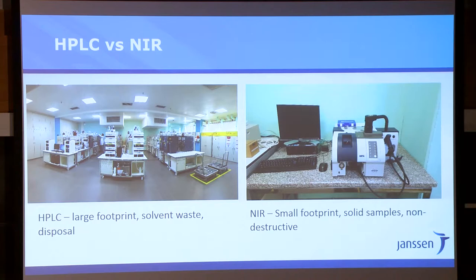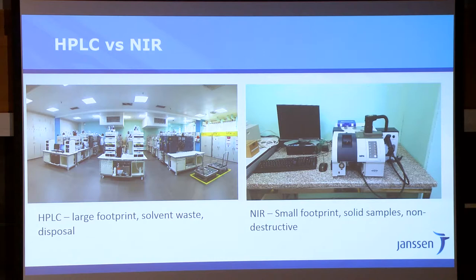The near-IR is a small piece of equipment with a small footprint and none of the environmental impact. The savings just from that have been quite real. On the left is a schematic of our continuous line — you feed from the top, you blend, you compress, and eventually you coat. When you do this in batch, you take samples two or three times during production from a batch of tablets that's been all mixed up, so you don't know whether a given tablet was made early or late. You can have a batch of 10 million tablets and you're only sampling six tablets three times — so if there are issues with some tablets, the chance of detecting it is very low.